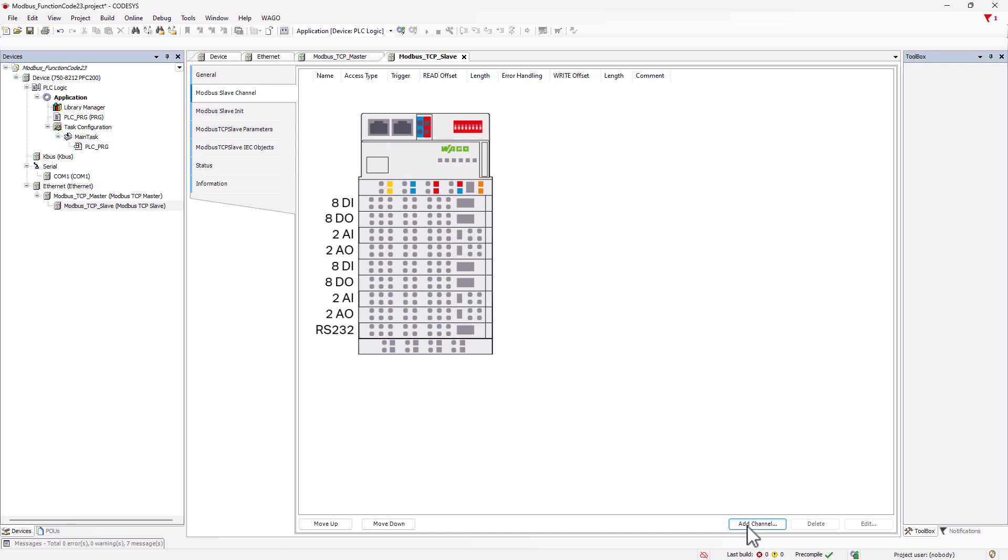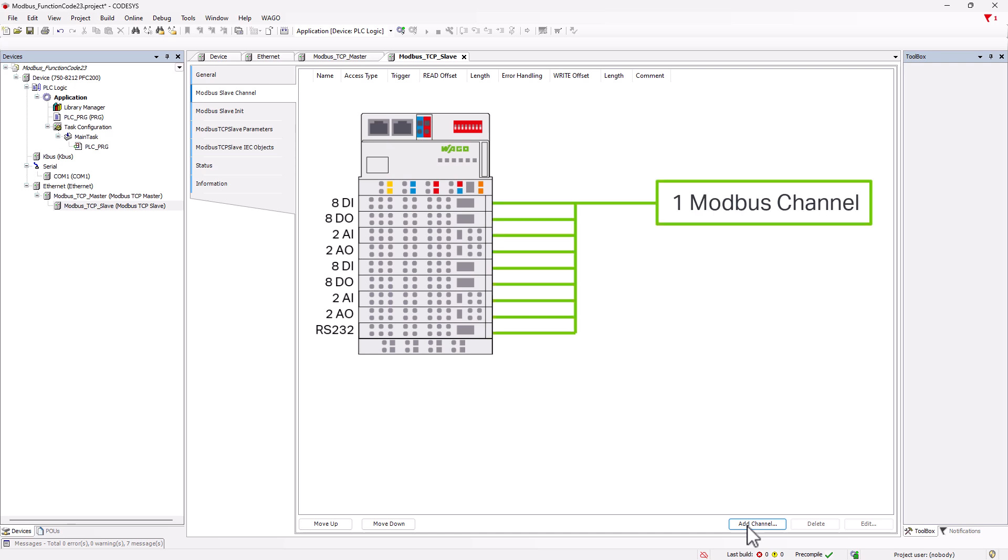But why not read and write the entire node with all connected modules in a single channel? And this is exactly the method we want to explain in detail here. In CodeSys 3.5, there is the function code 23, read-write multiple registers for this purpose.